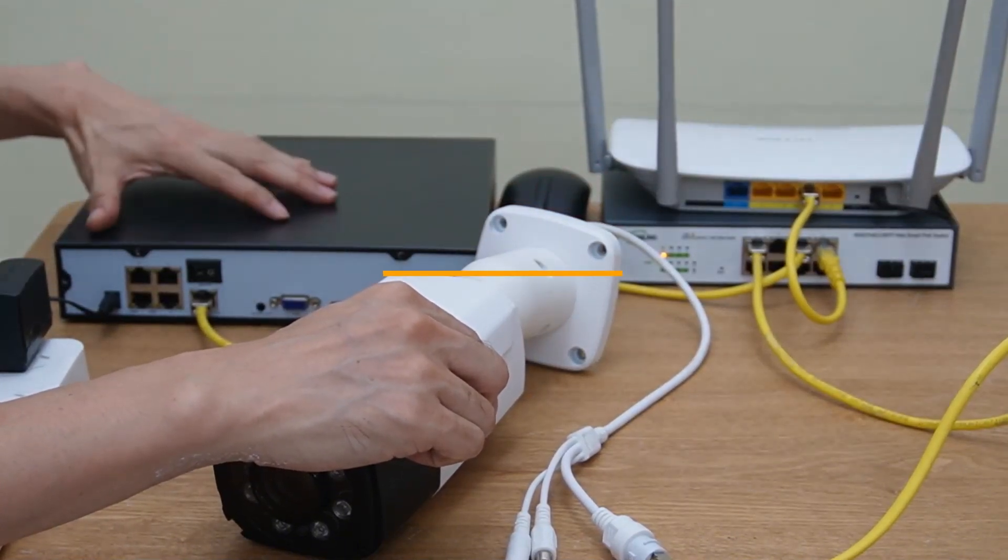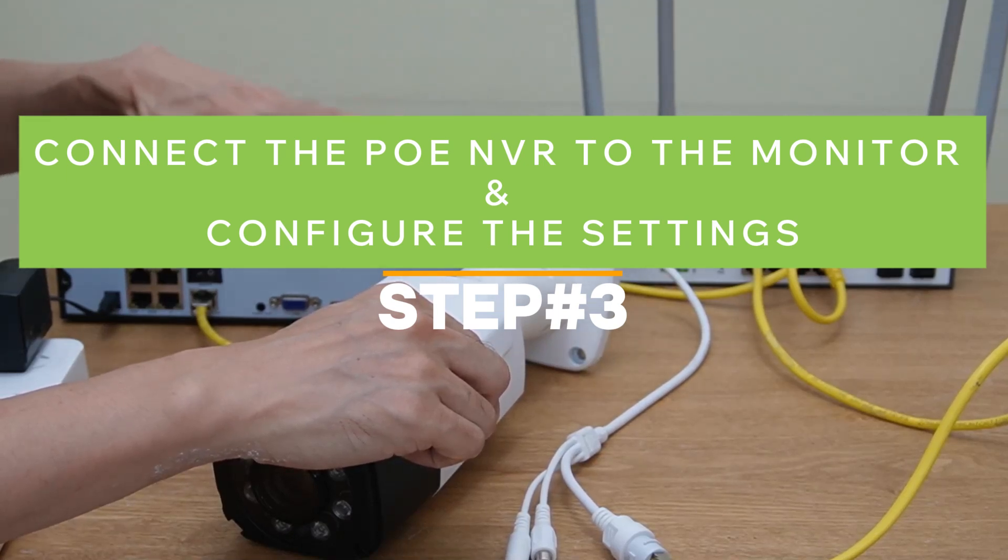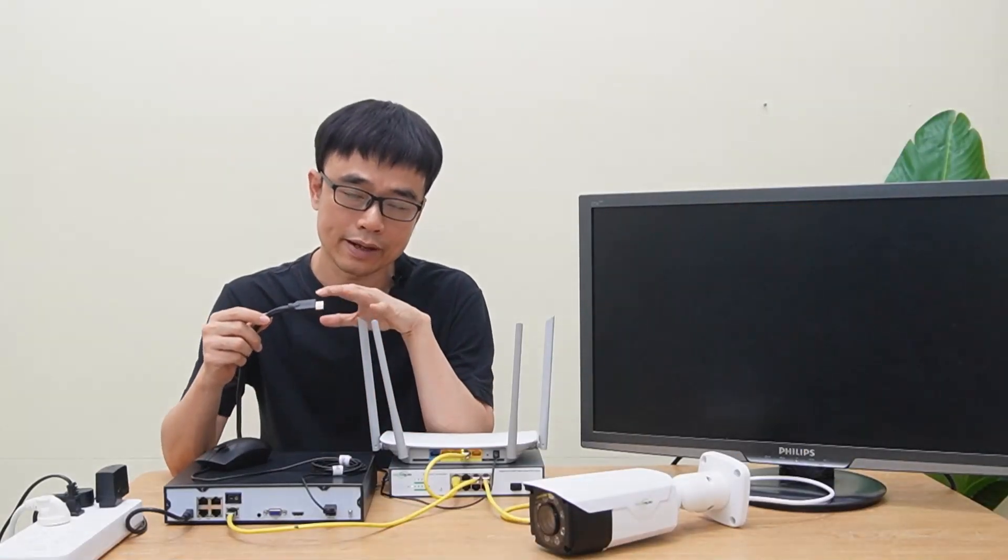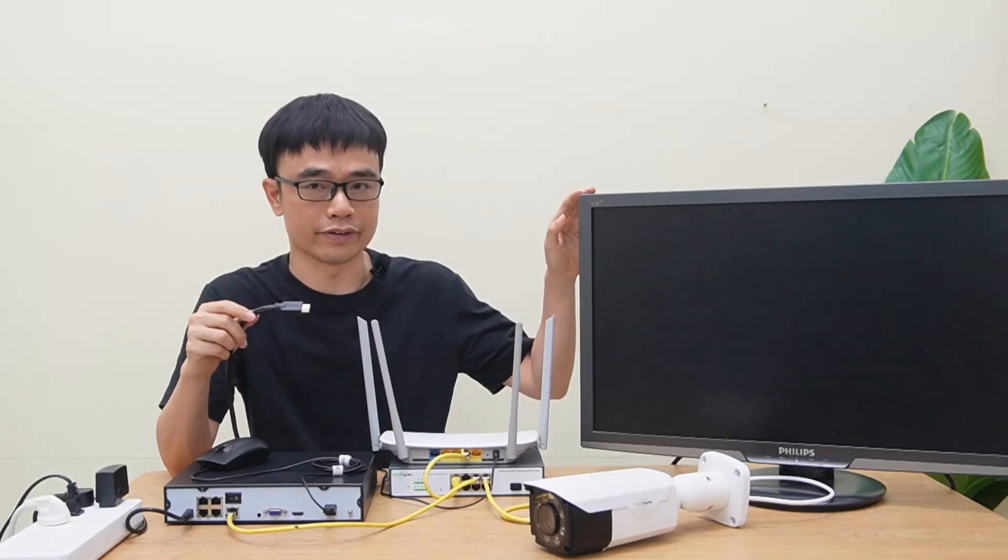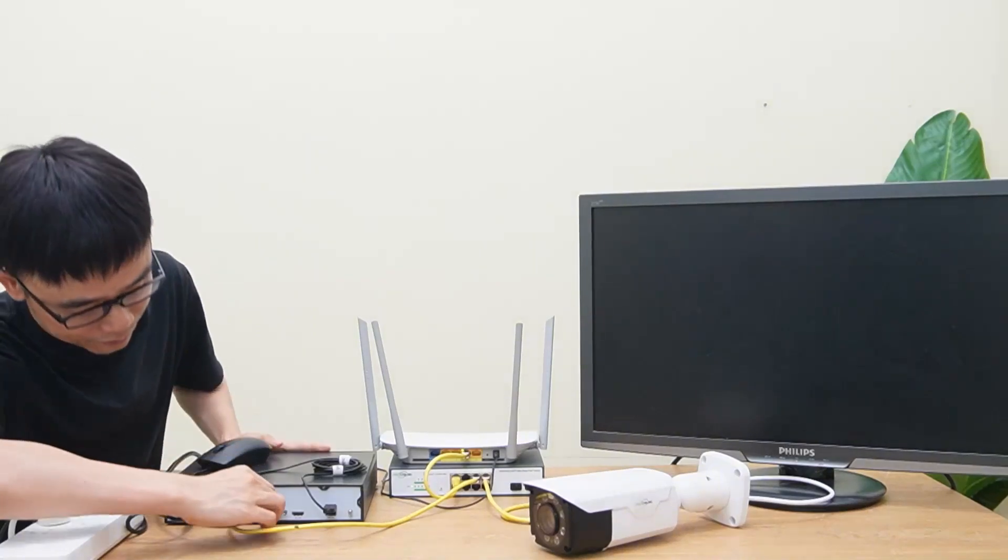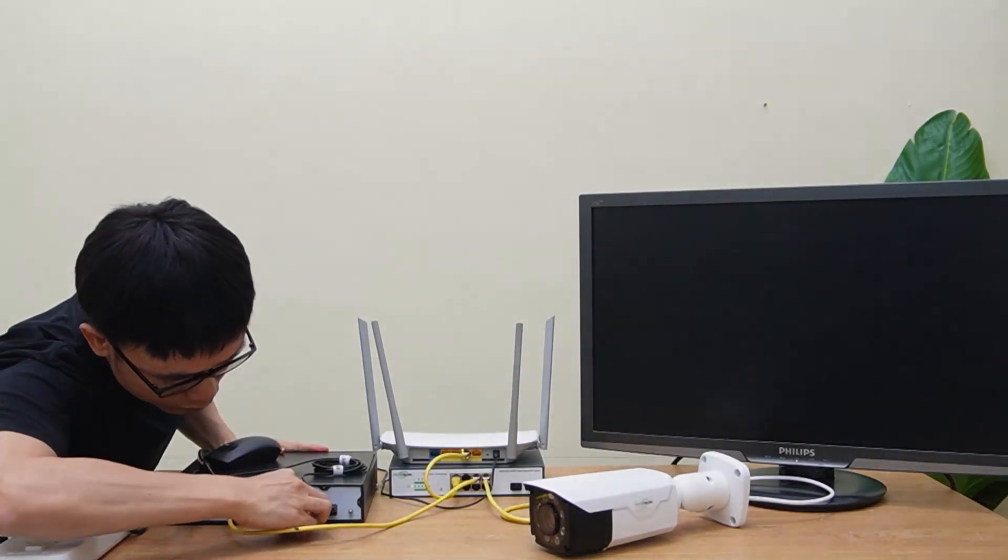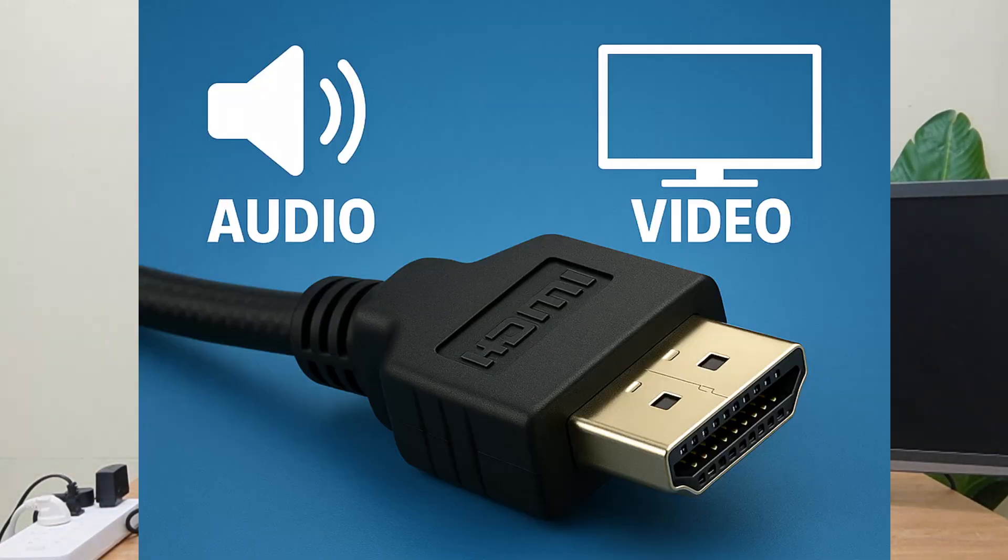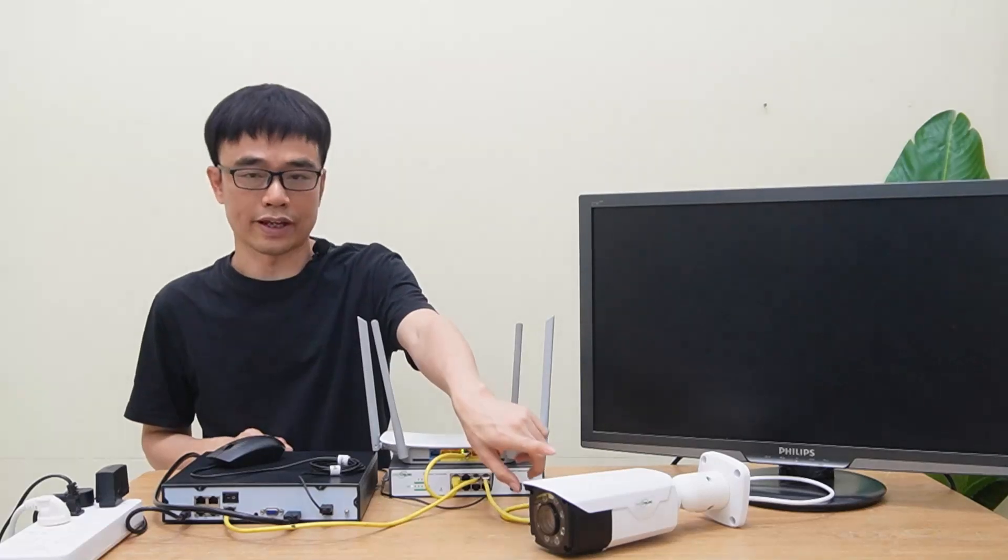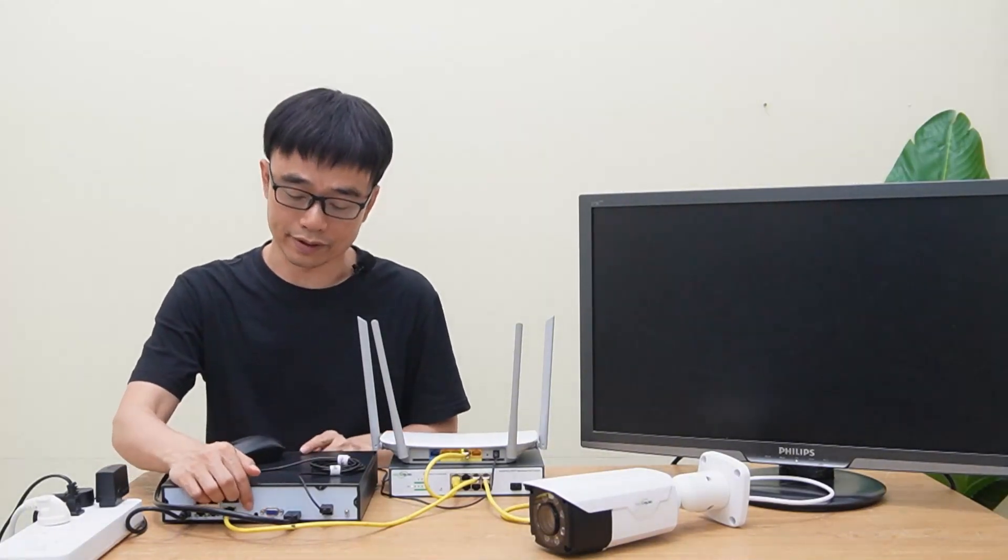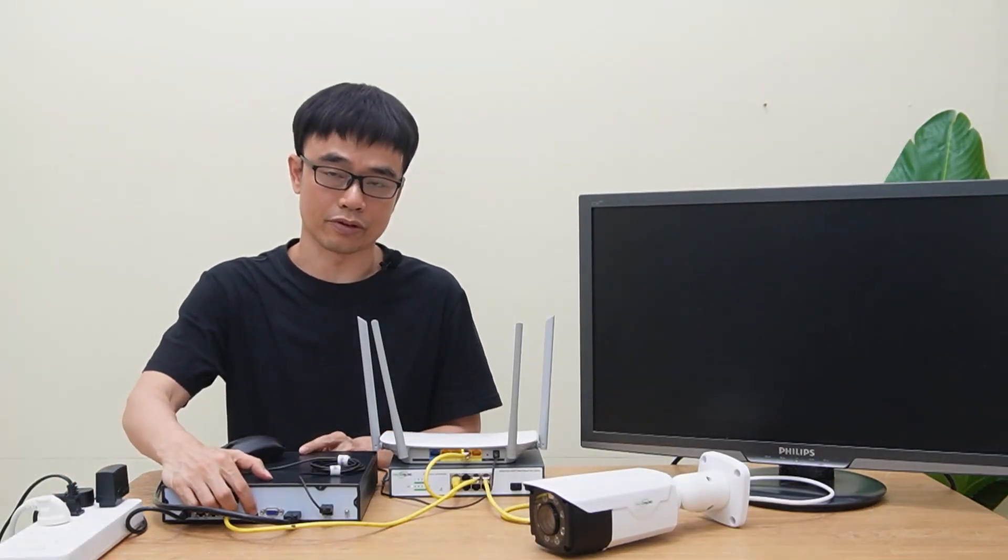Let's connect this network video recorder to our monitor and try to configure the setting on the NVR. This is the HDMI cable. Another end of this cable has connected to the HDMI port on this monitor. Let's connect the cable to the HDMI port on the NVR. The good thing to use HDMI cable is it supports both audio and video. If there's audio built-in in your camera, you can hear the audio on the TV directly. If you just use the VGA port, you probably need to connect the speaker to the external audio output on your network video recorder.